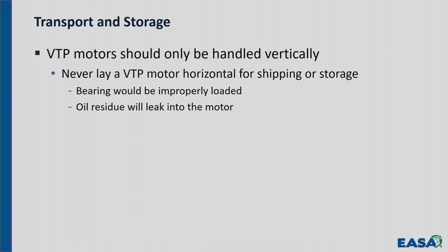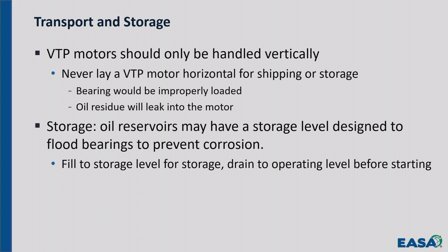The other reason is the oil. If there's any oil left, it'll start leaking and start to run out, and you can create oil problems that way. When you store it, some of the vertical motors have a different oil level marked on the sight glass for storage, and it'll be higher if they raise the oil level up to completely submerge the bearings so there's no air there to avoid corrosion to the bearings. If they're completely submerged in the oil, they're protected. Okay? And then you've got to drain that oil back out before you start the motor and operate it.